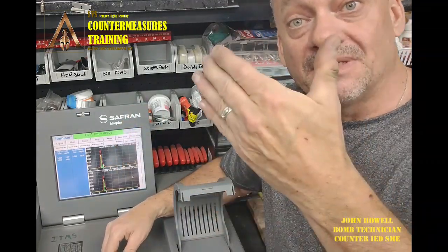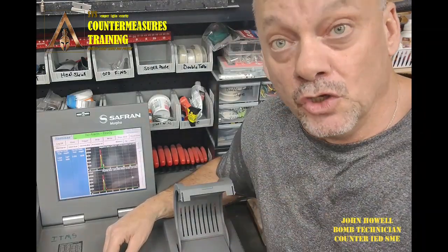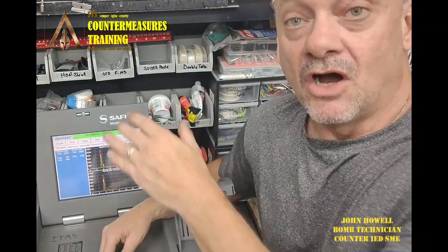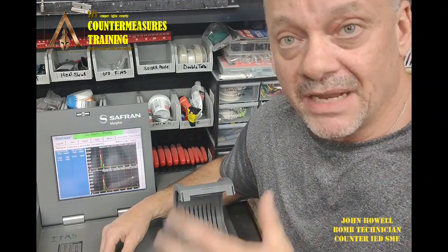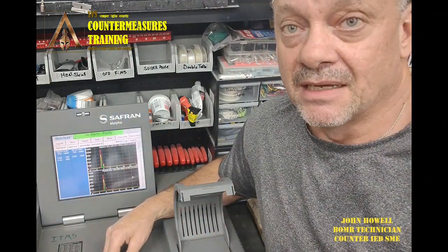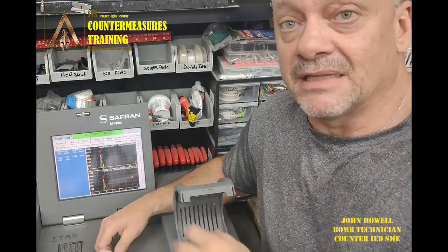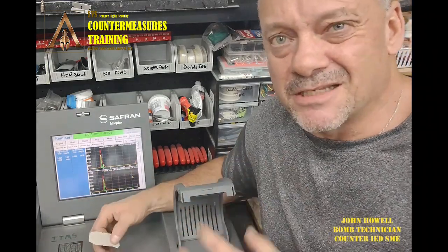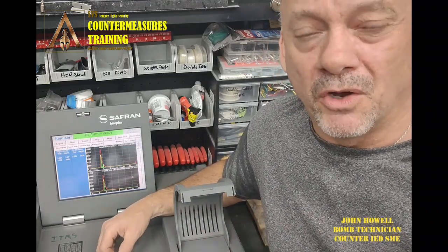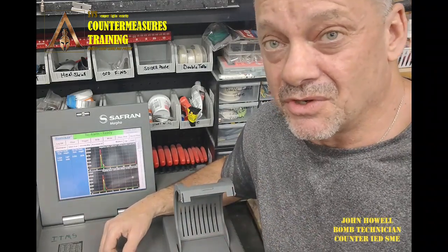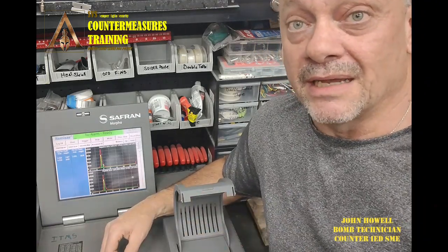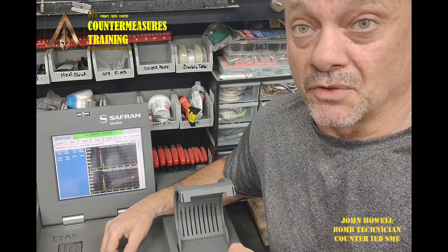Okay, so as you go up in temp or go down in temp, you lose detection capability on either the positive and the negative mode depending on where you're looking for those explosives at. All right, so that's the first part of explaining this technology, and one of the biggest things people get confused about is the dual mode and how important the temperatures are on what program you're running to make sure this system's going to work for you the way you want it to work.